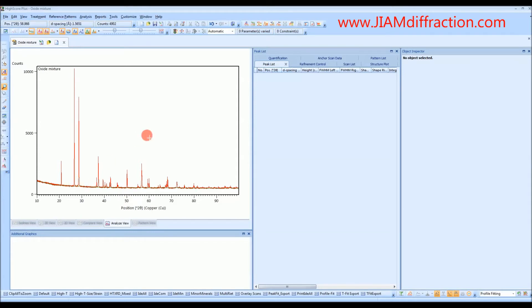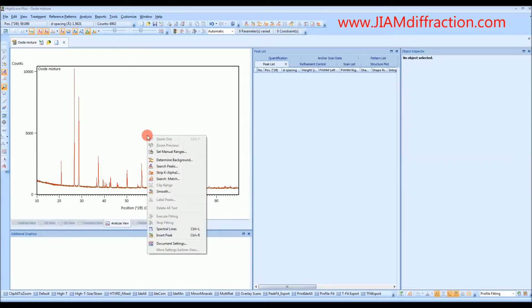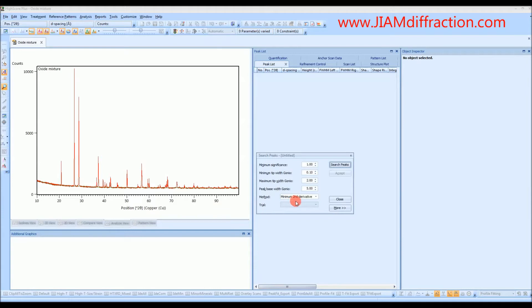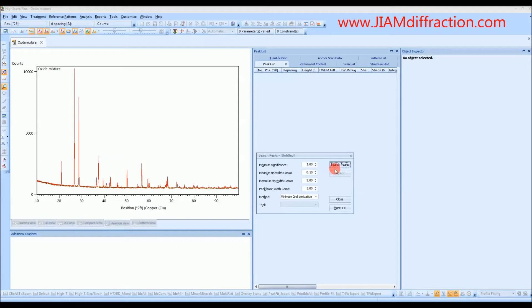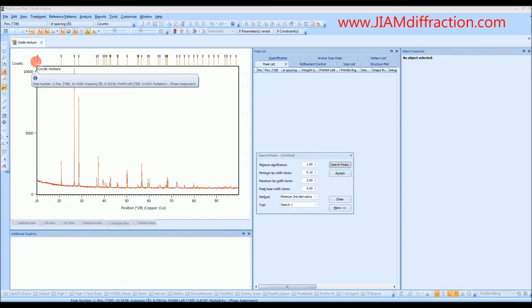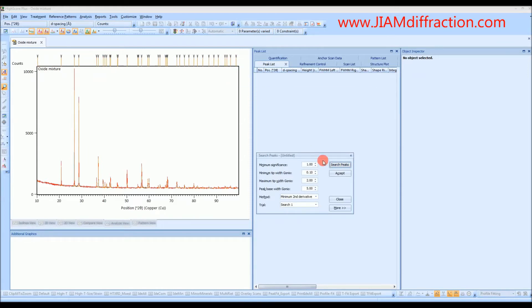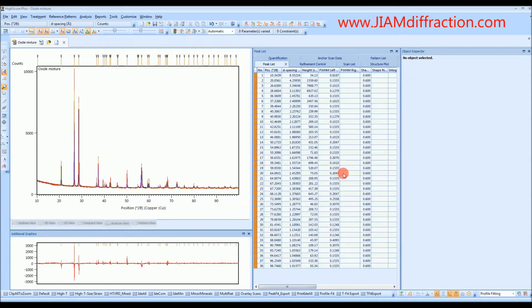The next step is not really required but it is nice when you're trying to do phase identification. If we right-click and go to search peaks we can start to try to tell the software what is a peak and what isn't a peak or we'll let the software determine that. We have some parameters here that we could change in order to help the software figure out what is a peak and what's just noise. I don't usually change these. I'll just search peaks. We see a bunch of data markers along the top so a lot of peaks have obviously been found. So for now I will just accept. We see the peak list now here under peak list.